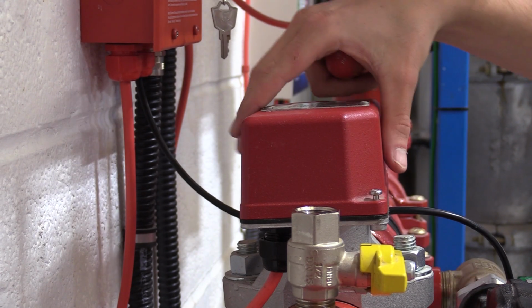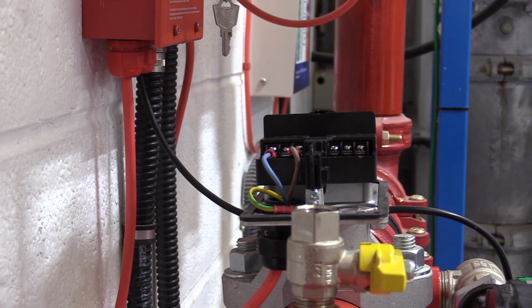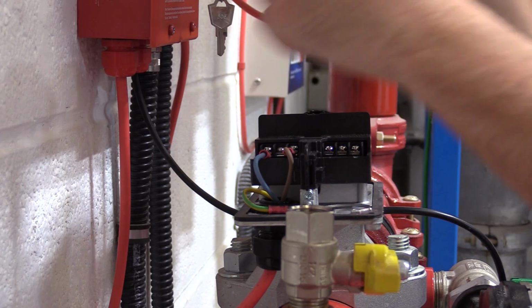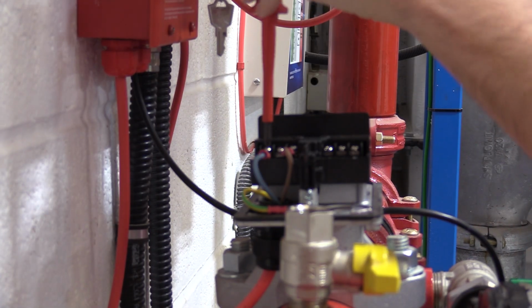Check wiring of flow switch by removing the lid and checking that wiring is secure and is using the correct terminals, normally open and common.